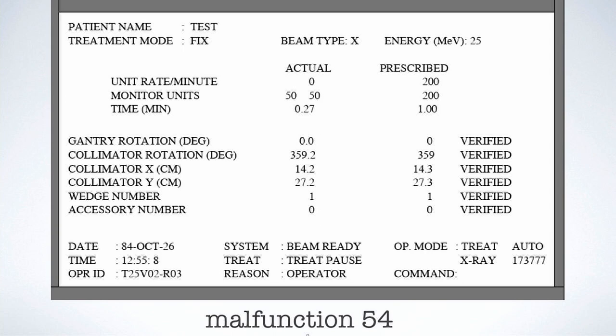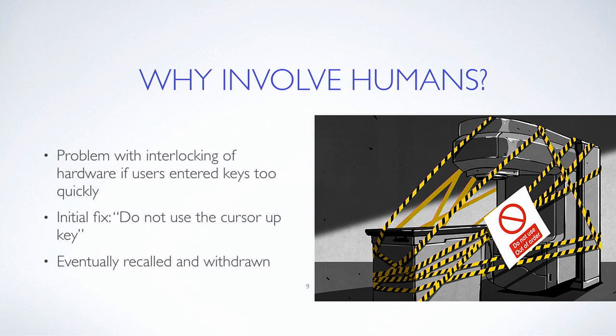There are lots of problems with the Therac-25 — many are engineering issues such as race conditions and lack of documentation, which are beyond the scope of this talk. But one major issue was only discovered because one radiotherapy technician was present during two incidents and noticed the malfunction 54 error message. One interface quirk allowed cursor movements on the keypad during calibration — if the user selected x-ray mode, the machine would begin setting up for high-powered x-rays, a process taking eight seconds. If the user switched to electron mode within those eight seconds, the turntable would not switch to the correct position, leaving it in an unknown state with no feedback to the user.